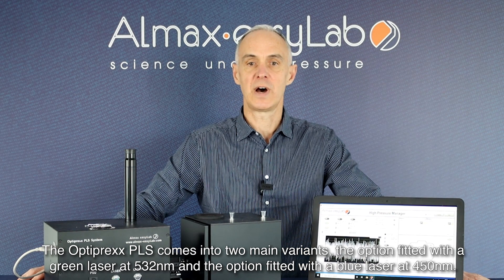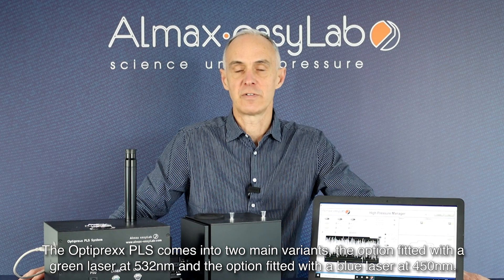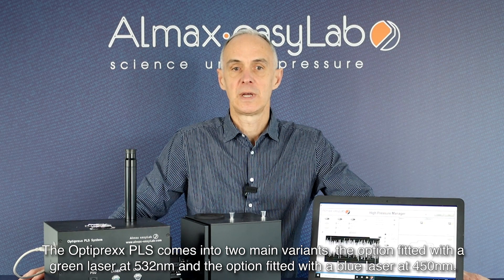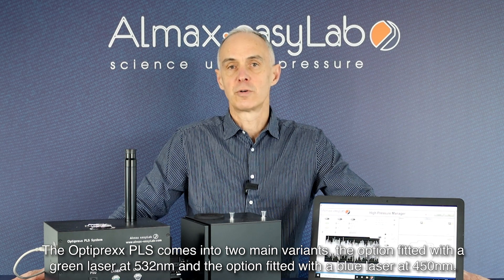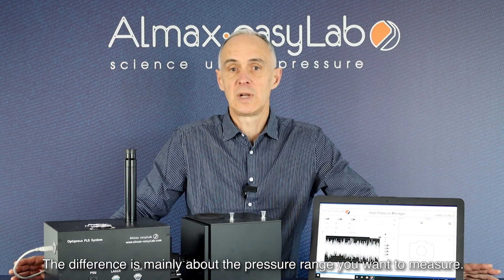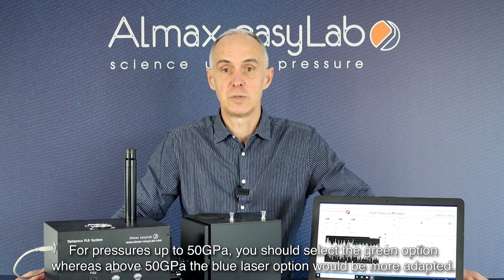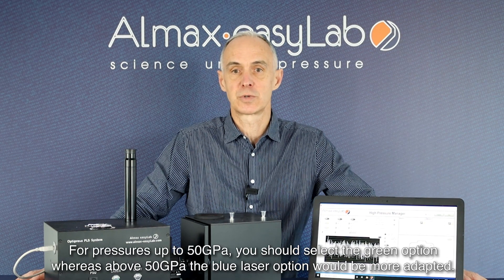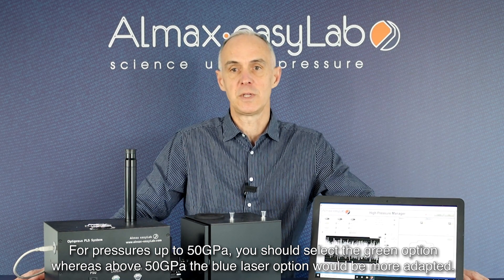The Optiprexx PLS comes in two main variants: the option fitted with a green laser at 532 nanometers, and the option fitted with a blue laser at 450 nanometers. The difference is mainly about the pressure range you want to measure. For pressures up to 50 GPa, you would select the green option, whereas the blue laser option would be more adapted for pressures above 50 GPa. Both versions deliver an output power of 50 mW.